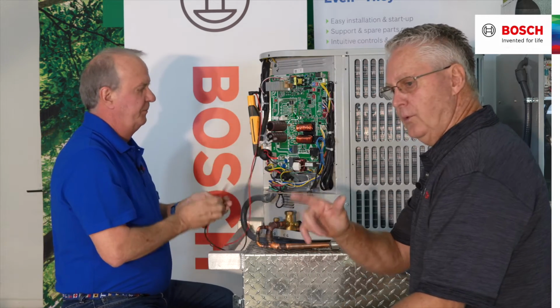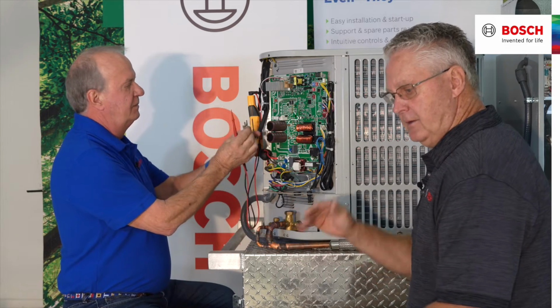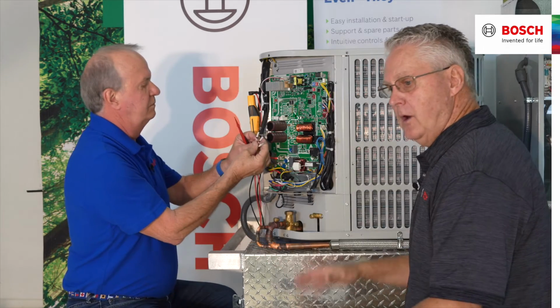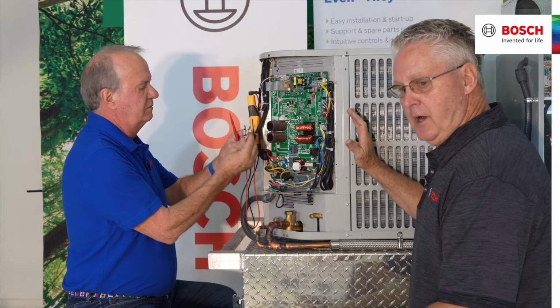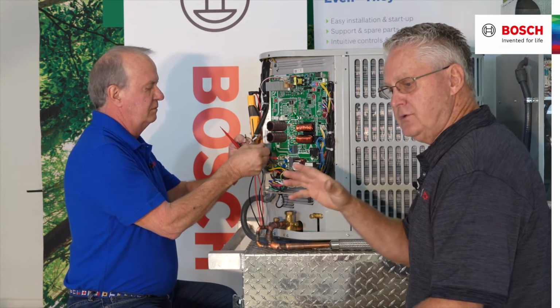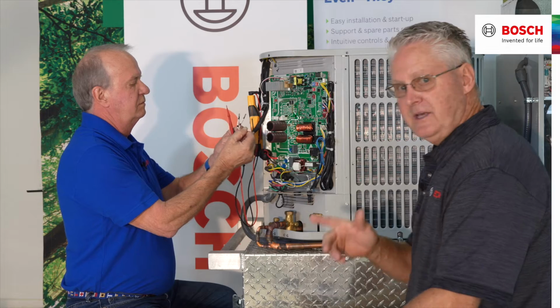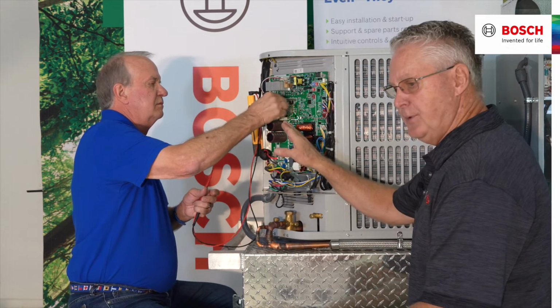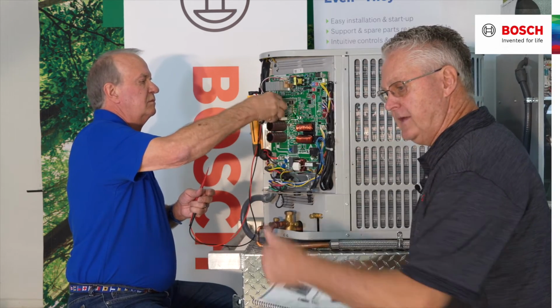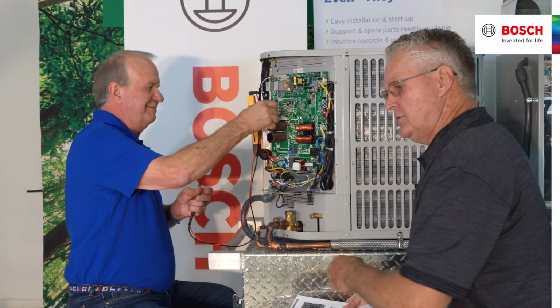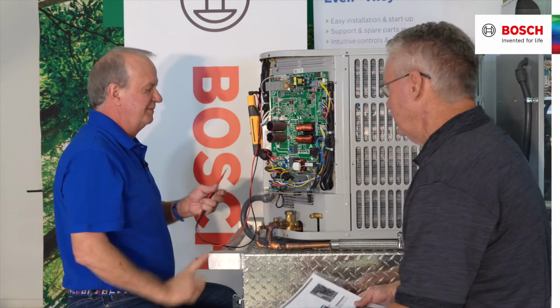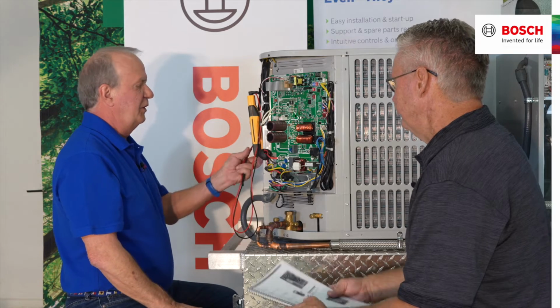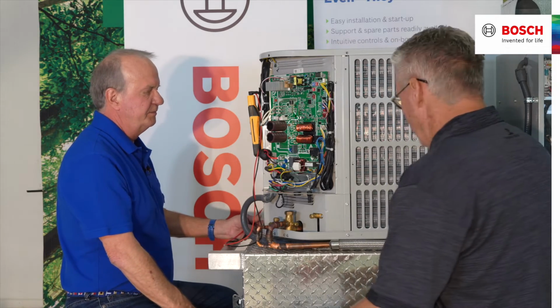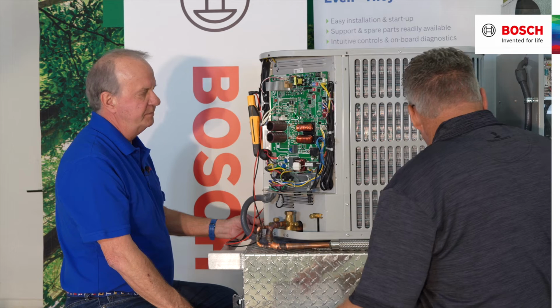1.2. Again, less than 1.5. On the 5-ton Bosch unit, the number that we would be looking for is less than 1. Now when Ken's putting the wires back on, we're making sure that the U goes to the U, the W goes to the W, and the V goes to the V. Got it all done? Correct. Awesome. Good to go. Now we can power this unit back up.